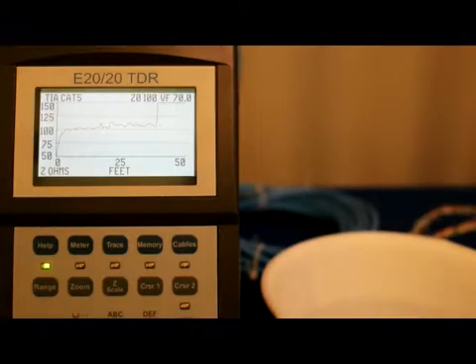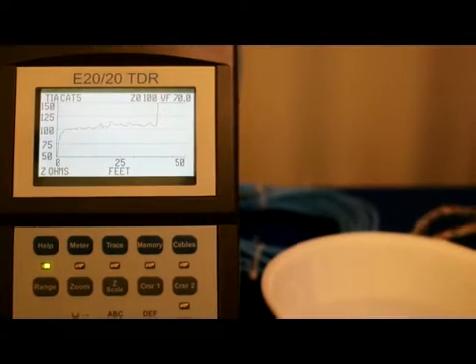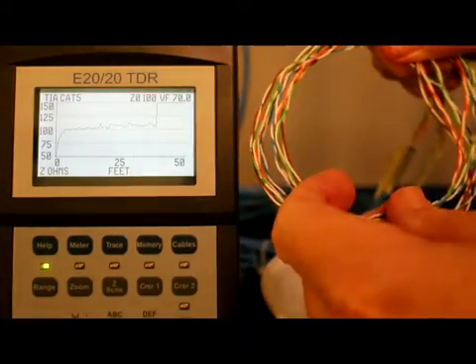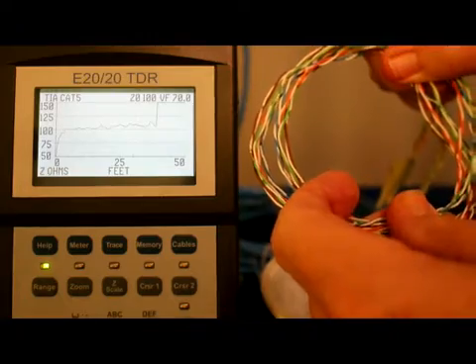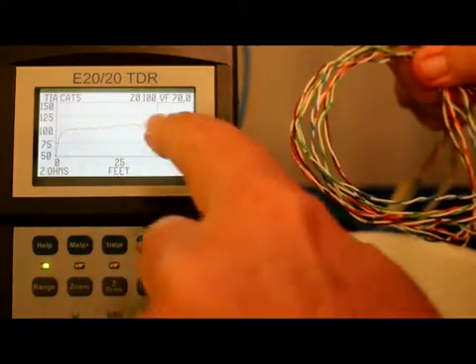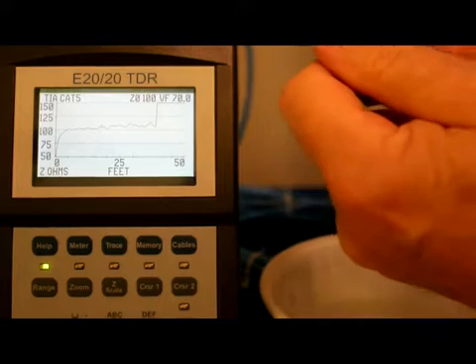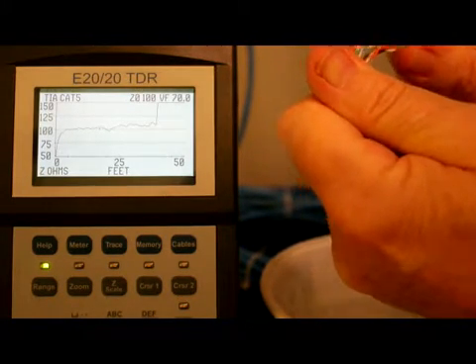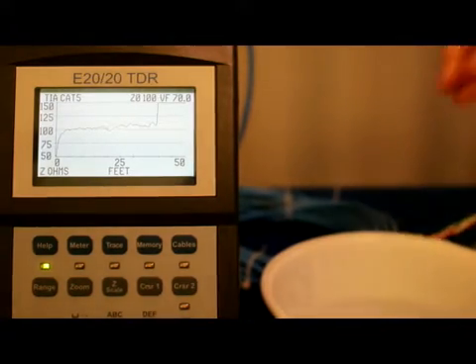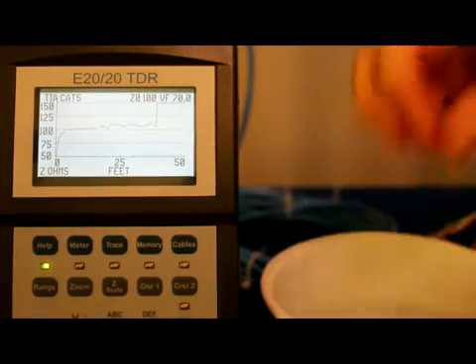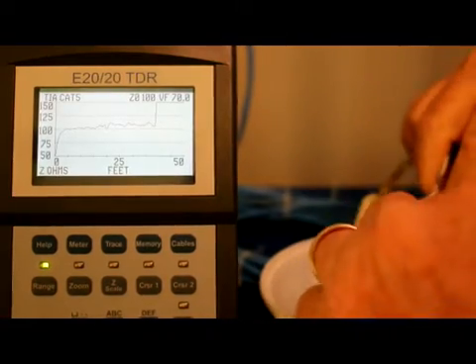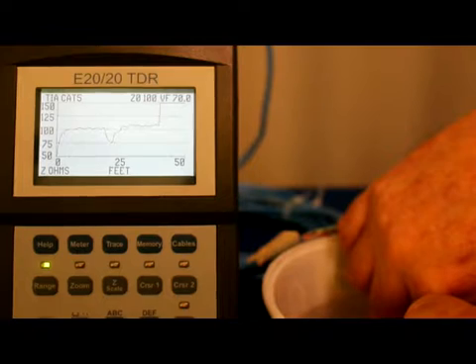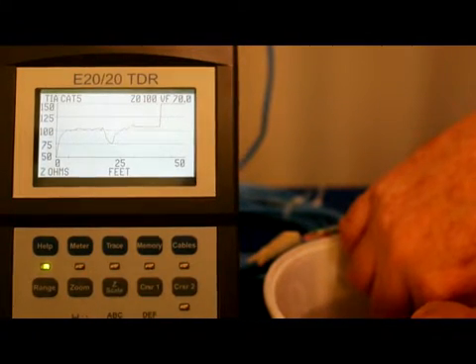In our last test, we'll demonstrate what water or even a little moisture looks like in a twisted pair cable. For demonstration purposes, our victim cable has its jacket removed. When I dip the pairs in the water, it reduces the impedance between the wires significantly. The liquid does not have to be water — oil, hydraulic fluid, fuel, any liquid will induce this effect. Wet cable traces will vary in appearance but will always be an erratic downward excursion in the impedance. Additionally, the velocity in wet cable changes to some unknown value, so measured distances in or after the water cannot be trusted.